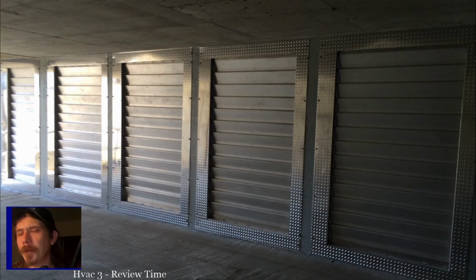That's cool. Anyway, low water cutoffs. If you look in the code book, if you ever read the mechanical code, low water cutoffs are required for every boiler system, period. The only way you can get around not having a low water cutoff is to have a flow switch on the system so that it monitors that there's actually flow through the boiler. They will generally accept that you not have a low water cutoff as long as you have some sort of flow switch.